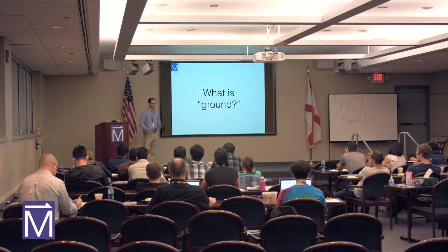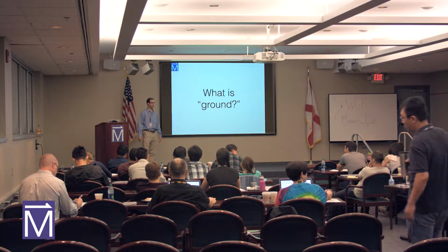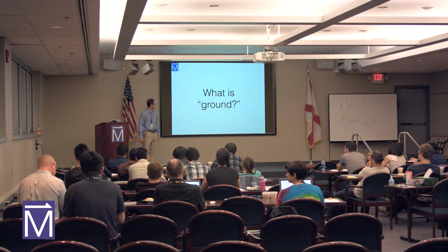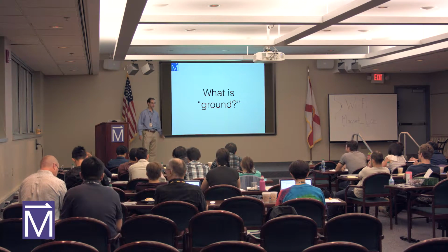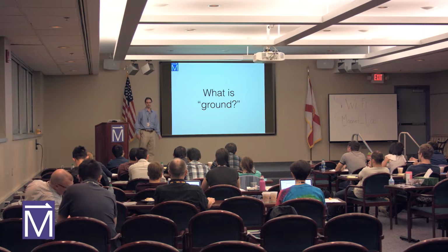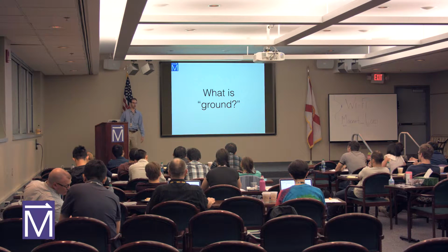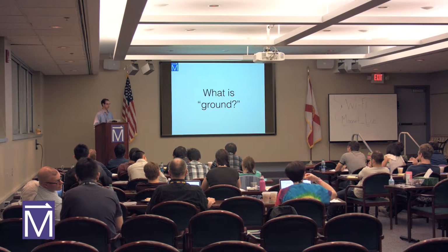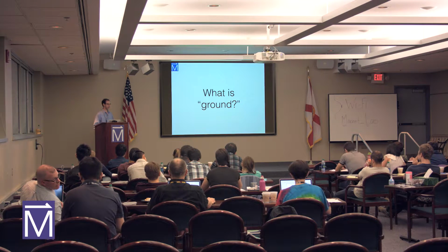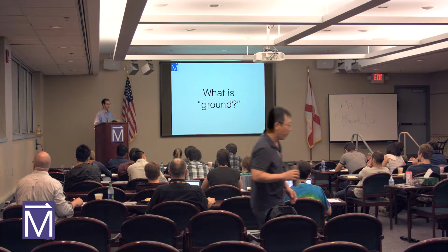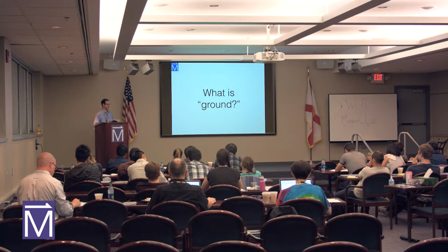Okay. Now, what is ground? You've heard this from, again, at least 3 presentations. I hate the word ground because I really don't know what it means. And I think about this all the time. To me, ground is anything that's actually at 0 potential, which is basically, we define the Earth as being at 0 potential. So the surface of the Earth is 0. Everything else is something slightly different from ground because we have to connect something resistive to it. Even a really nice long ground rod is not quite at ground.